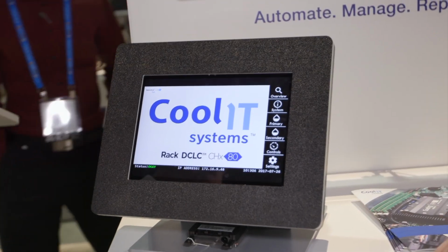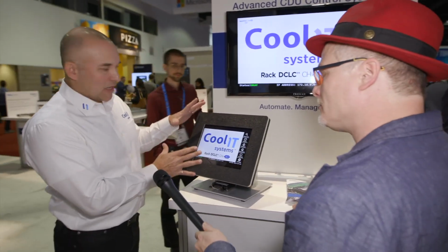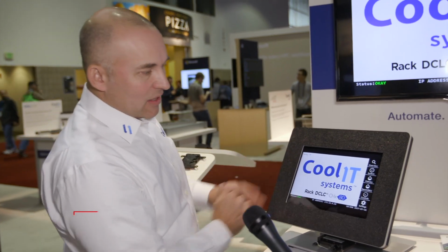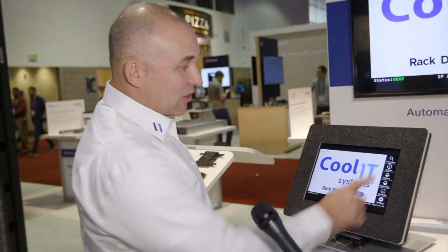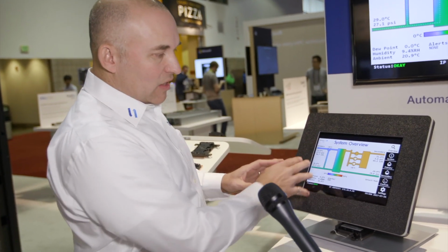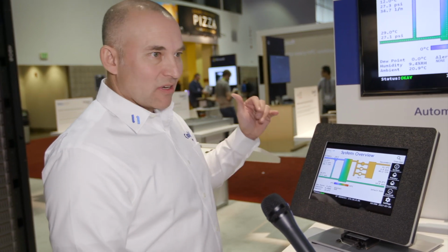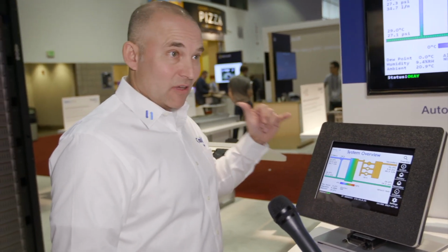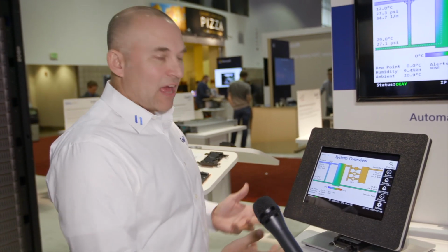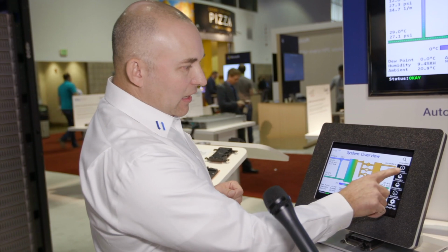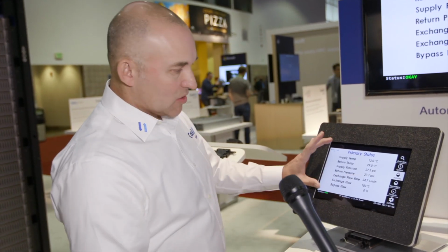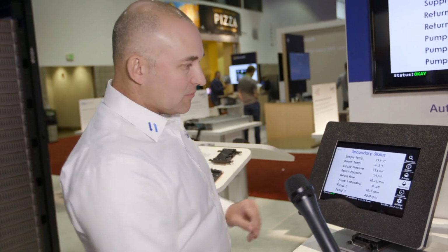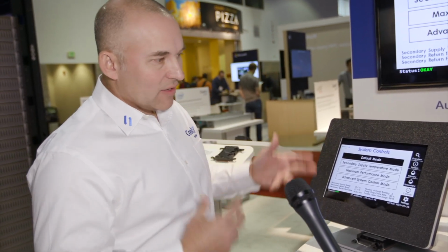So, Jeff, is this the interface we were talking about? That's right. So this is a duplication of what you would see on the front of any of our heat exchanger products. So it has detailed information that you might want to have for configuration or settings or even just checking how it's doing. So it features an overview that'll tell you how many pumps are running, what percentage of their capacity they're running at, what your flow is, the temperatures of the primary and secondary, the temperatures of the inlet and outlet, so it can even calculate how much heat it's dissipating. Inside here, you can get even more detailed information on what's going on with primary, secondary. With the controls, you have a couple of different modes.